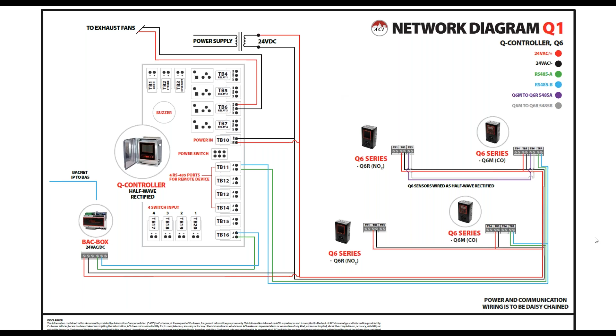Here would be just a typical network diagram. For example, this happens to have a Q controller on it, which goes up to 128 digital points. We only show 4 sensors, but let's say we had 60. The RS-485 would be pretty much all the same. And then we have a BAC-Box on there that you need to add if you want to come back to your BAS with BACnet IP. Just a typical diagram here.